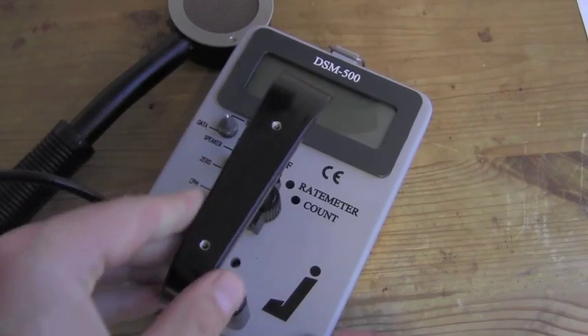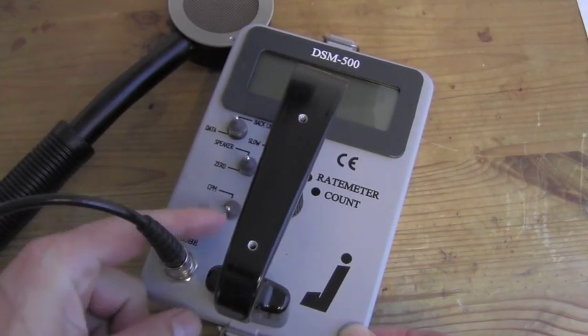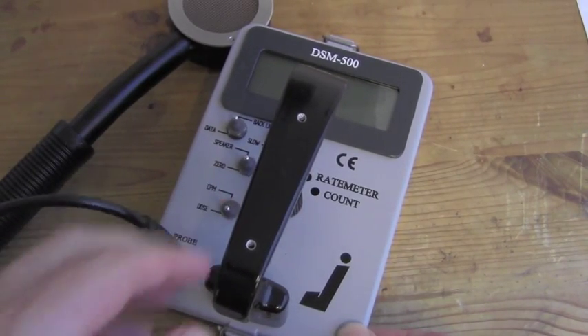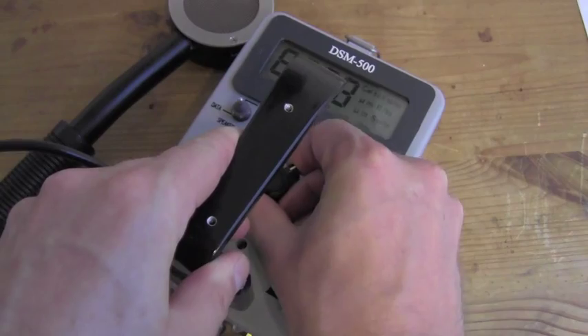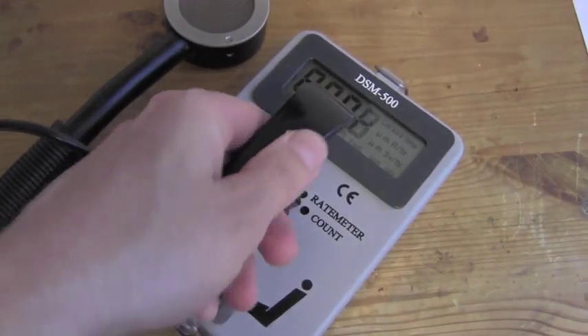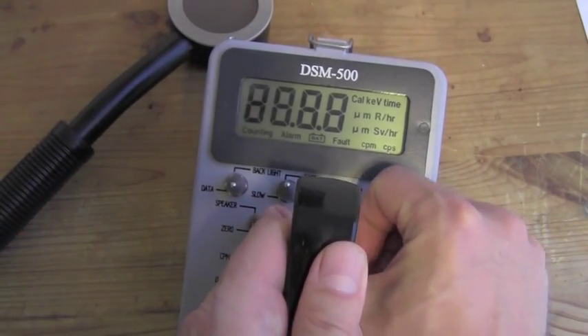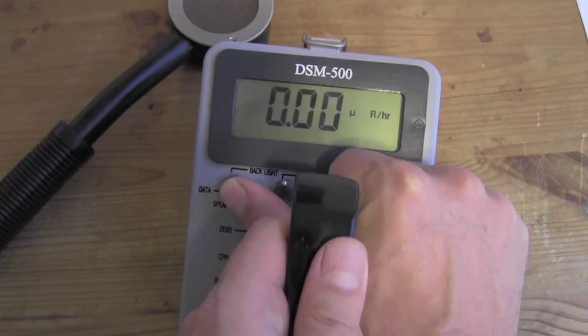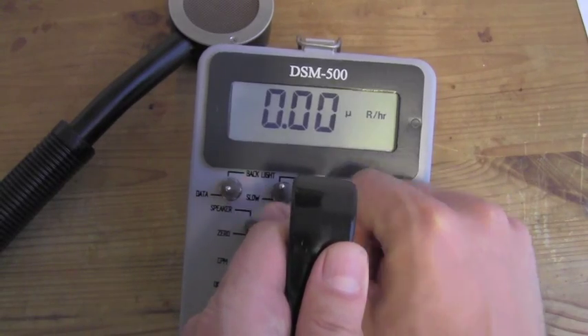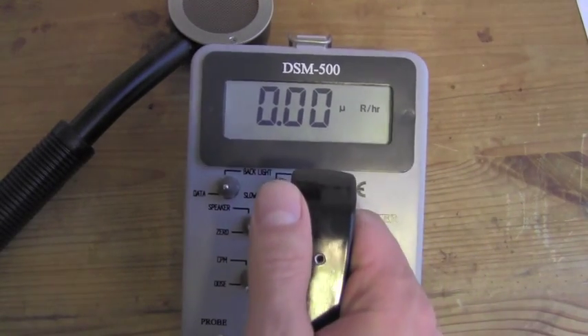First we are going to turn it on to the rate meter function, making sure it is in the dose mode. We are going to turn it on to zero and turn the backlight on for nice readability.